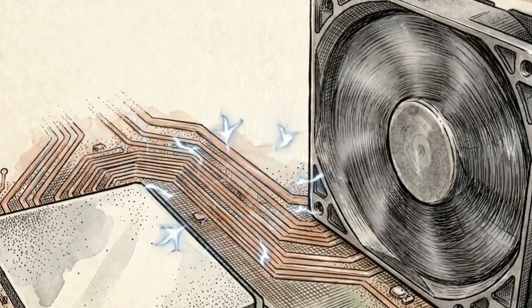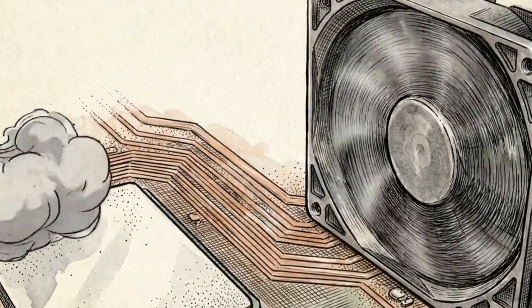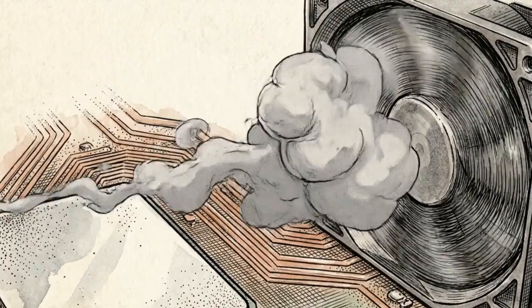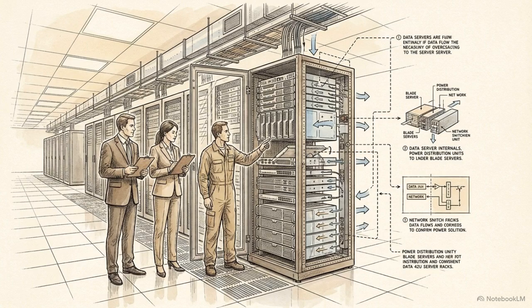Only the out-of-band BMC has the resolution required to track these specific inlet gradients and fan curves. In high-density AI environments, detecting these slow burn signals via the BMC is the only way to prevent catastrophic thermal cascades. Beyond physical uptime, hardware telemetry is now a matter of legal compliance.